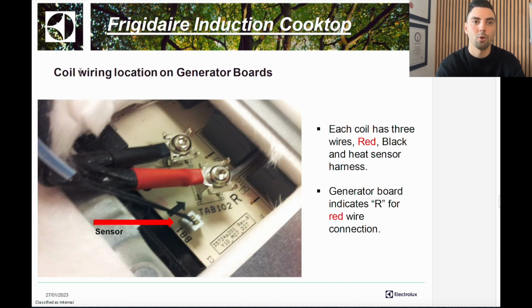Coil wire locations on generator boards. So each coil has 3 wires, red, black, and heat sensor harness. Generator boards indicate R for red wire connection. You need to make sure that it's always connected in the proper location. Otherwise, you'll get an inactive component.